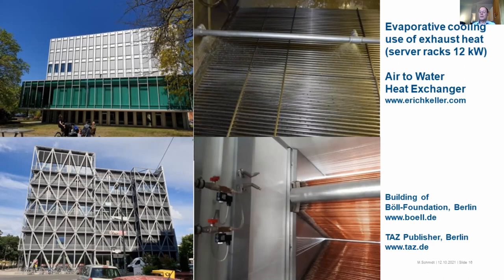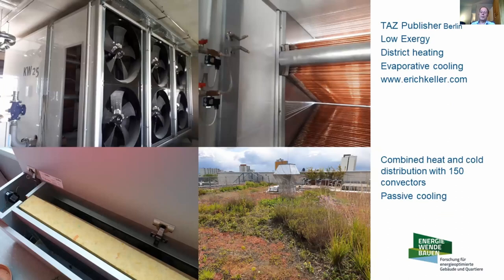This is a view inside, so you can activate, for example, your walls or ceilings in your building. In these buildings, we are using these convectors, because with convectors in this shape, you can work with a difference of 8 to 9 to 10 degrees. So you can heat your building with 30 degrees coming from a heat pump, or cool your building with 18 or 19 degrees coming from these evaporative cooling systems.